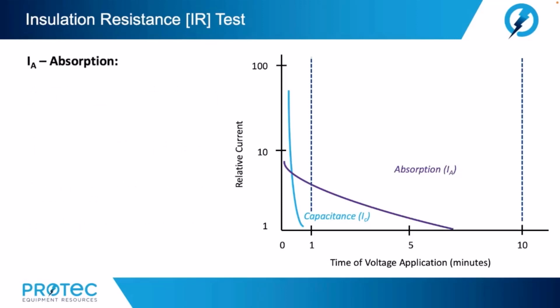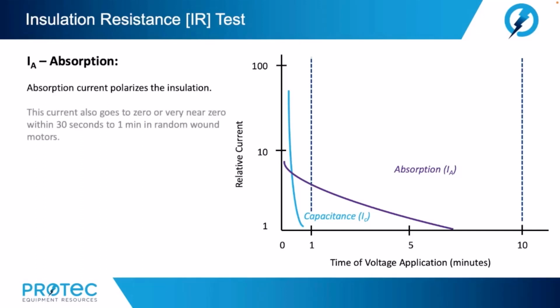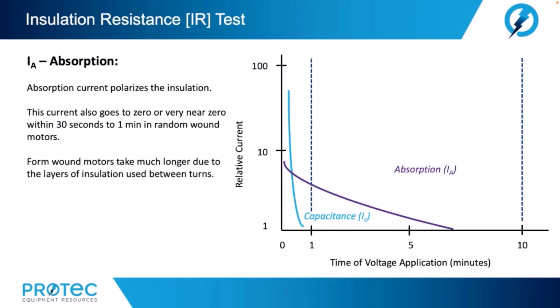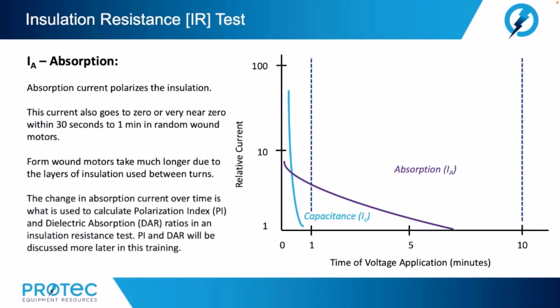We also have a thing called absorption current. Absorption current polarizes the insulation. This current also goes to zero or very near zero within 30 seconds to 1 minute in random wound motors. Form wound motors take much longer due to the layers of insulation used between turns. The change in absorption current over time is what is used to calculate polarization index and dielectric absorption ratios in an insulation resistance test. The PI and DAR will be discussed more a little bit later in this training.